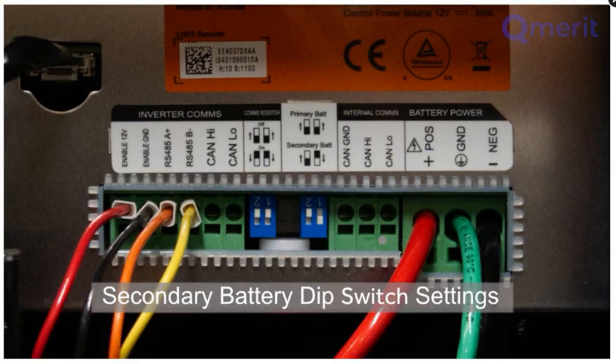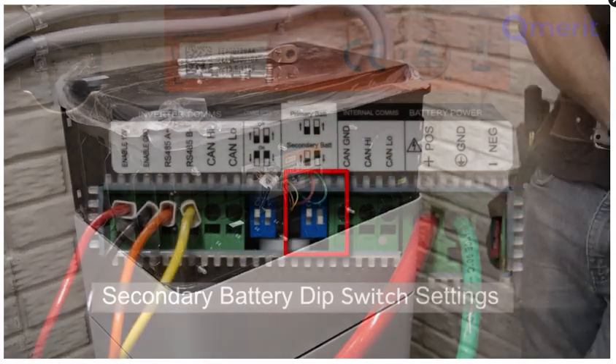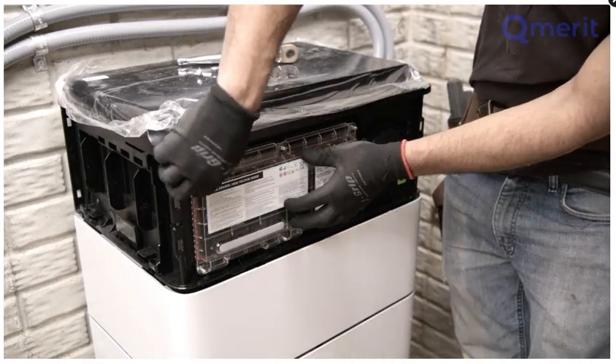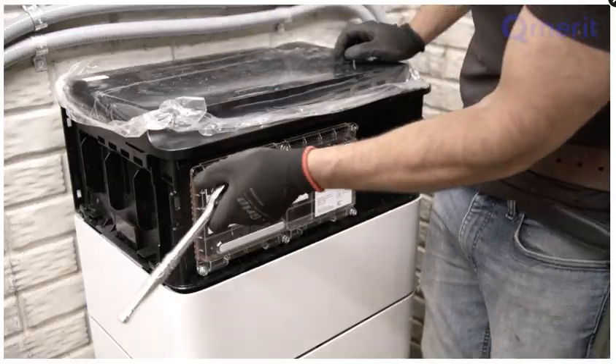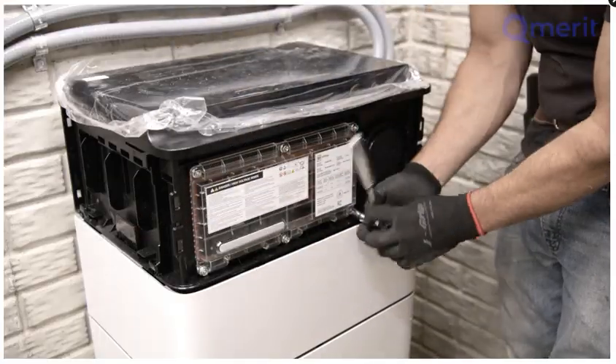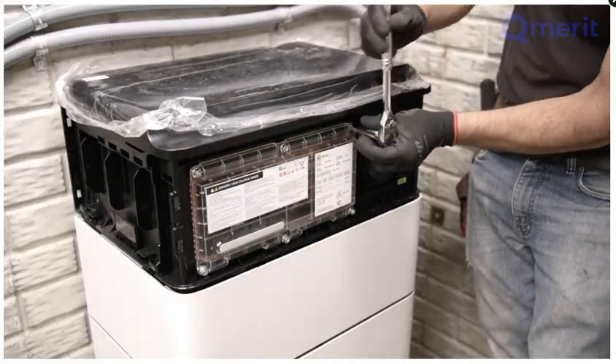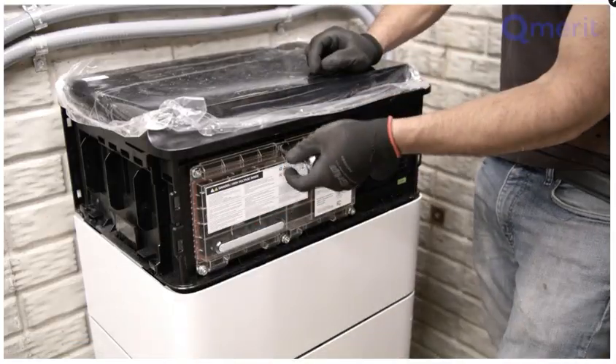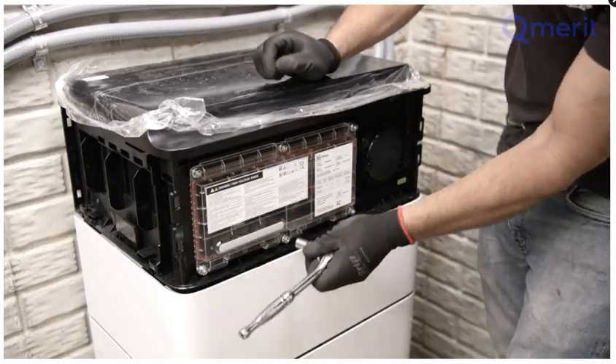If this were a secondary battery pack, we would set the 2 dip switches on the left to the up position. Regarding the 2 dip switches on the right, the first dip switch will be set to the up position and the second dip switch to its right will be set to the down position. The wiring to the BCU is complete. Install the front cover panel. Do not install the outer cover until wiring is complete to the GM bidirectional inverter because the circuit breaker in the BCU will need to be turned on.